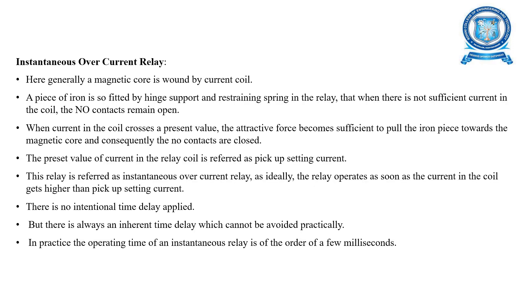First is the instantaneous overcurrent relay. Here, a magnetic core is formed by the current coil, and a piece of iron is fitted via a hinge support with a restraining spring, such that when there is insufficient current in the coil, the normally open contacts remain open. When the current in the coil crosses the preset value, the attractive force becomes sufficient to pull the iron piece towards the magnetic core, and consequently the normally open contacts are closed.